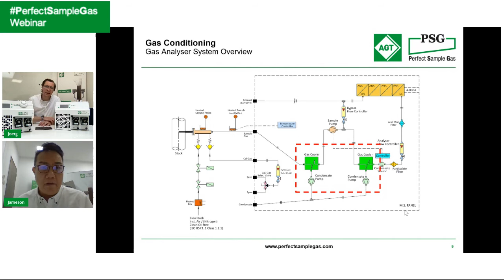Many times, it's always good to oversize the sample pump. If I were the system integrator, I would also want to oversize the sample pump to buffer any additionally needed flow. However, having an oversized sample pump, sometimes we overlook that it is oversized so much that it exceeds our gas cooler specification. When the capacity is exceeded, the sample flow rate is so fast that it passes through, and you can see water carry over like this.